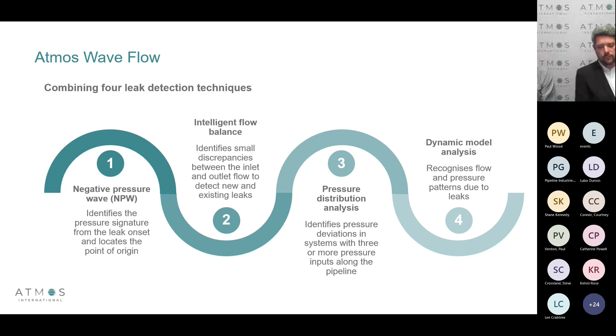So what you're seeing here is the negative pressure wave principle happening. You can see a leak occur and the negative pressure wave traveling up the pipeline. We have installed PTs, sampling at that high acquisition rate, and we're able to see that small change in pressure associated with that leak and provide an accurate leak location from that. Now you have the advantage, especially when we're talking about the water industry, that I know it's very important to detect your existing leaks on the pipeline, but more importantly, you need to be able to detect these new leaks forming so they don't just add to the pot of existing leaks.